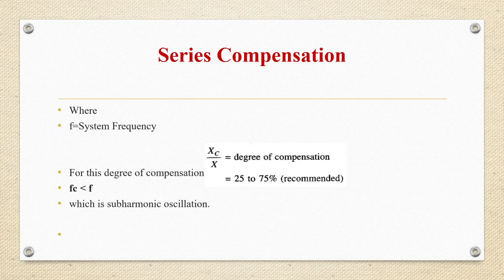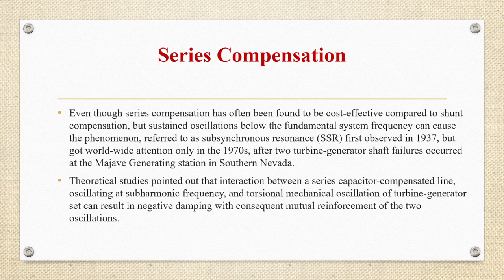So it was first observed in 1937 but got worldwide attention in 1970s after two turbine generator shaft failures occurred at the Mojave generating station in southern Nevada. So theoretical studies pointed out that interaction between a series capacitor compensated line oscillating at subharmonic frequency and torsional mechanical oscillation of turbine generator set can result in negative damping with consequent mutual reinforcement of the two oscillations. So subsynchronous resonance is often not a major problem, and low cost countermeasures and protective measures can be applied.